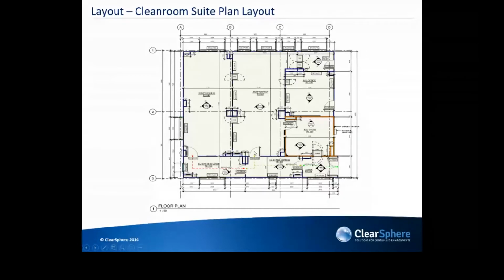You can come in here from the first stage into the second stage gowning, where you have to regown, and go into the compounding room from there where all the isolators are located. Back out here, you don't need to enter the facility, you can enter the aseptic office from outside. So the flow of personnel is controlled, coming from outside into the ISO 5, ISO 7 areas and so on, minimizing unnecessary traffic by the way the layout is done.